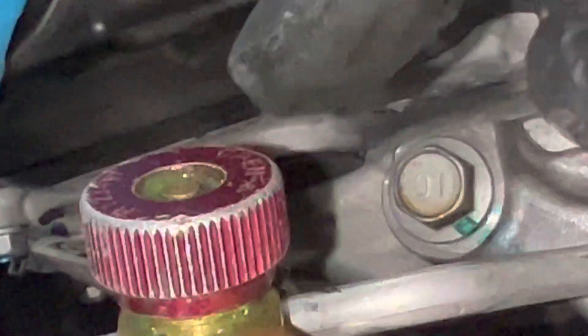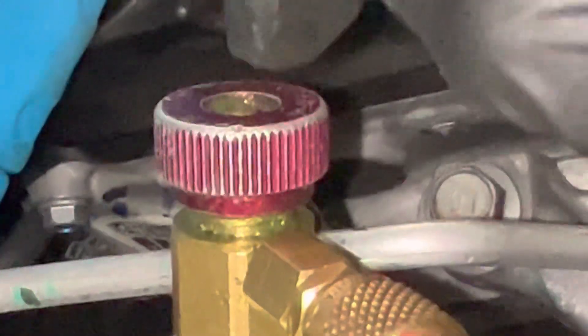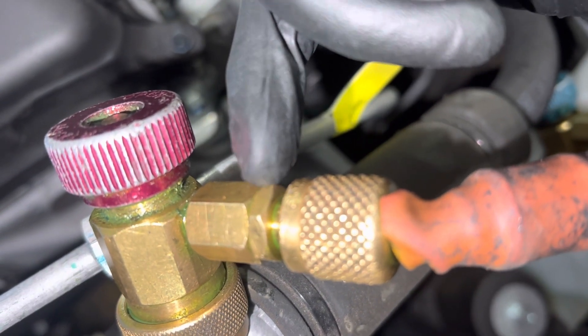If the leak is coming from the shaft that goes through the body — which has an o-ring inside — get Nylog or something similar and put it all the way around the circumference of the thread. Put your Nylog up where that shaft comes through, because that's the only other spot where a vacuum leak could get in. If the vacuum leak stops, you know it's the shaft o-ring.